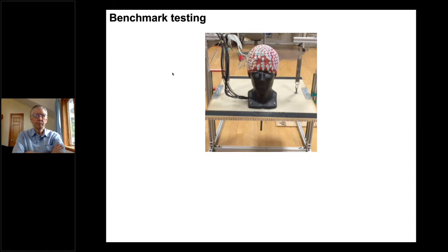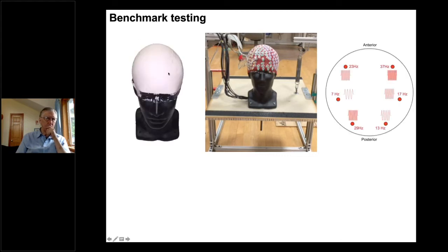In this case, what you're looking at is a mannequin head. Underneath of the electrode cap is a dental plaster material and there are wires going into this head creating voltage dipolar sources. So we can put EEG equipment on there and actually record what's coming through the head based on us knowing what we're putting into the head. So in this case, this is the dental plaster material. We have some sources embedded in the material. What I did in this case was I have six antenna that I put through sinusoidal bursting activity. Each one of the antenna is just doing this bursting activity totally randomized at very specific frequency.